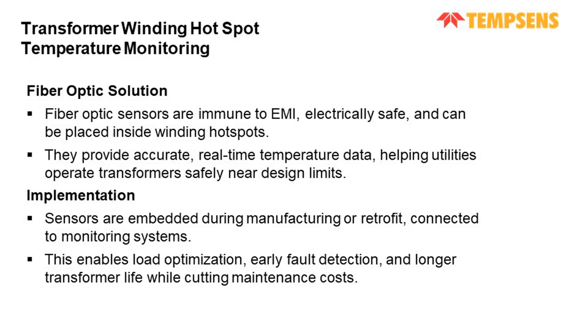So the fiber optic sensors can be installed directly between the windings, providing a real-time temperature of the windings, the places that get hottest inside the transformers. Okay, so by getting accurate real-time temperature data from these critical points, utilities can safely push transformers closer to their design limits without risking overheating. So this is the major benefit to the transformer companies in increasing the life of the transformer.